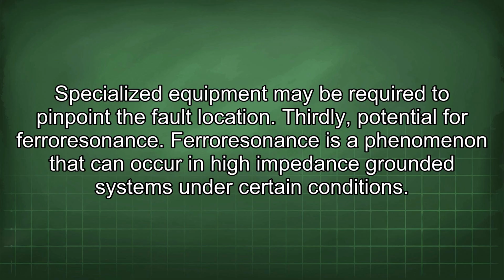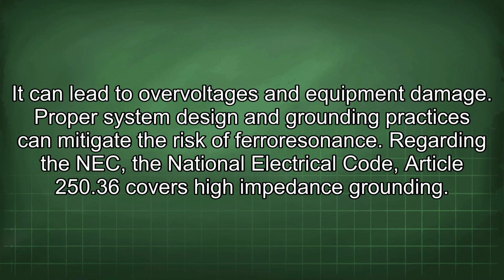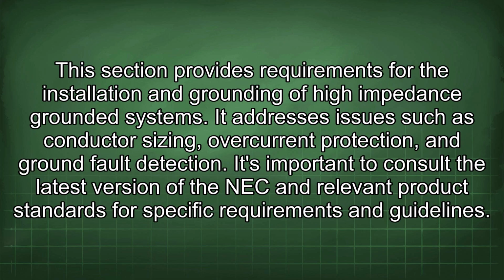Thirdly, potential for ferroresonance. Ferroresonance is a phenomenon that can occur in high-impedance grounded systems under certain conditions. It can lead to overvoltages and equipment damage. Proper system design and grounding practices can mitigate the risk of ferroresonance. Regarding the NEC, the National Electrical Code, Article 250.36 covers high-impedance grounding. This section provides requirements for the installation and grounding of high-impedance grounded systems. It addresses issues such as conductor sizing, overcurrent protection, and ground fault detection. It's important to consult the latest version of the NEC and relevant product standards for specific requirements and guidelines.